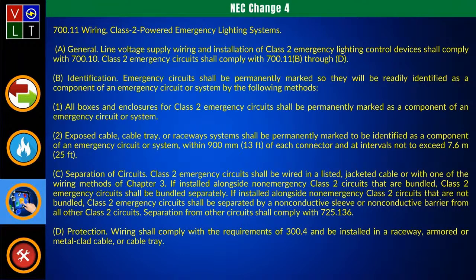All right, now this is going to deal with the wiring for your Class 2 powered emergency lighting systems, and it's got its general requirements, but it talks about identification shall be permanently marked for your emergency circuits. So, of course, they're readily identifiable. And then it talks about what are the following methods you could use to provide that? Well, you could have it at all boxes and enclosures for Class 2 emergency circuits. They should be permanently marked as a component of that system. Exposed cables, cable trays, or raceway systems shall be permanently marked to be identified as a component of an emergency circuit or system within 13 foot of each connector at intervals not to exceed 25 foot.